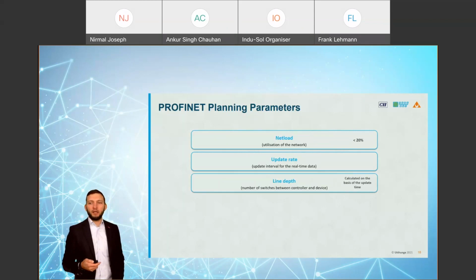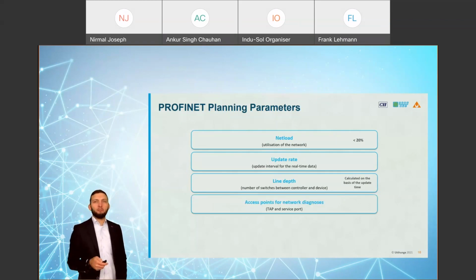Then line depth is also an important parameter. Line depth describes how many hops, or the number between my PLC and the last I/O device - it can be 7 hops or 8 hops. If we look at the PI guidelines, we find a little table where we can check if my planning passes for line depth.